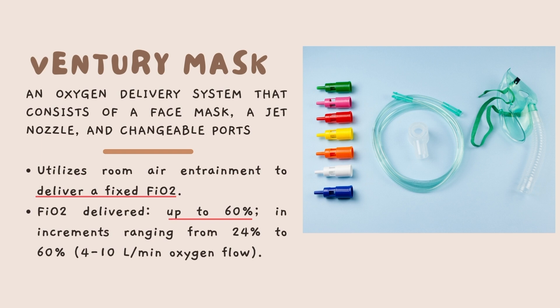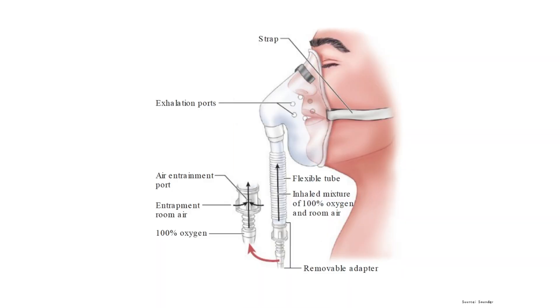Next we have the Venturi mask — an oxygen delivery system consisting of a face mask, a jet nozzle, and changeable ports. This system uses room air entrainment to deliver a fixed fraction of inspired oxygen. The FiO2 that can be delivered goes up to 60%, in increments ranging from 24% all the way up to 60%. The oxygen flow rate goes from 4 up to 10 liters per minute. It looks similar to the simple face mask but has air entrainment ports at the front.